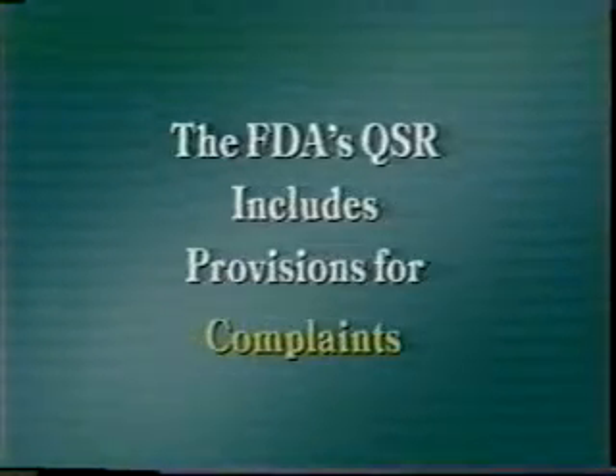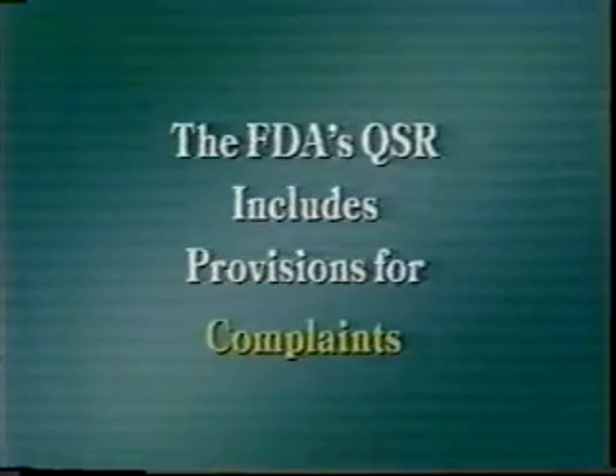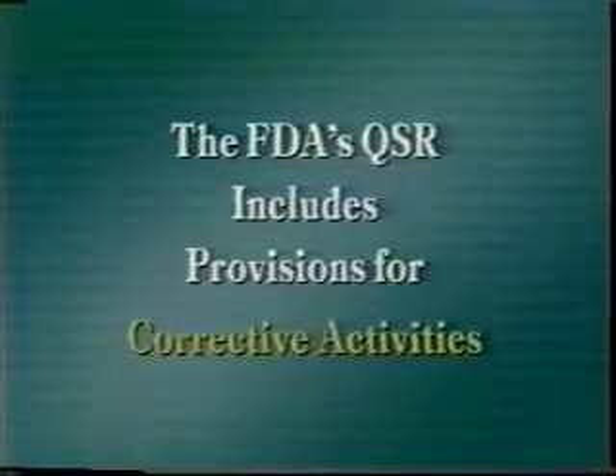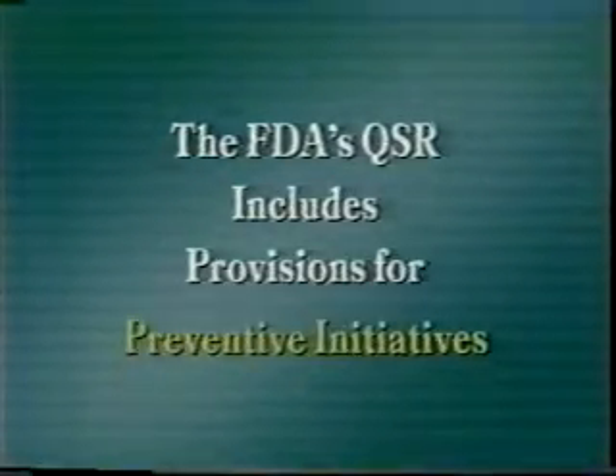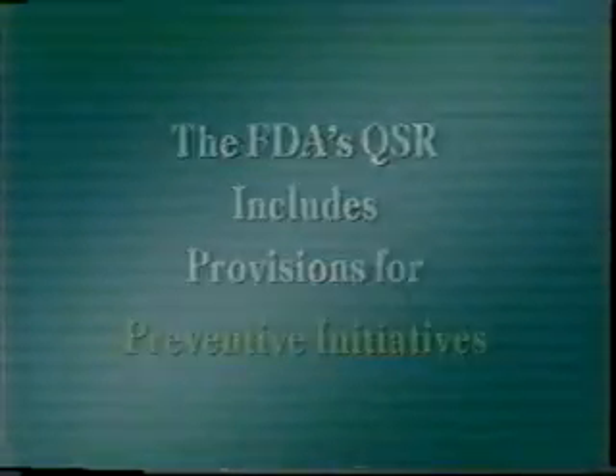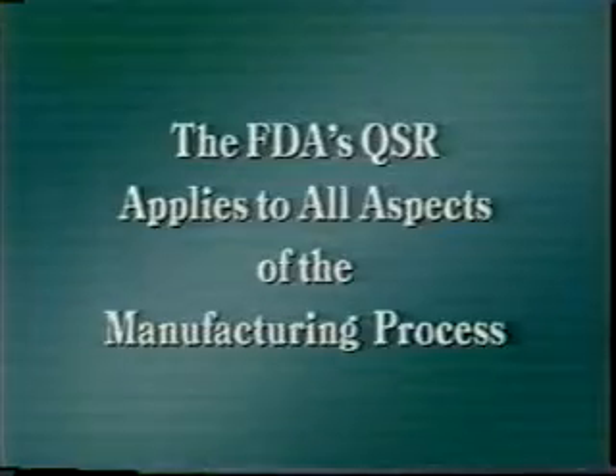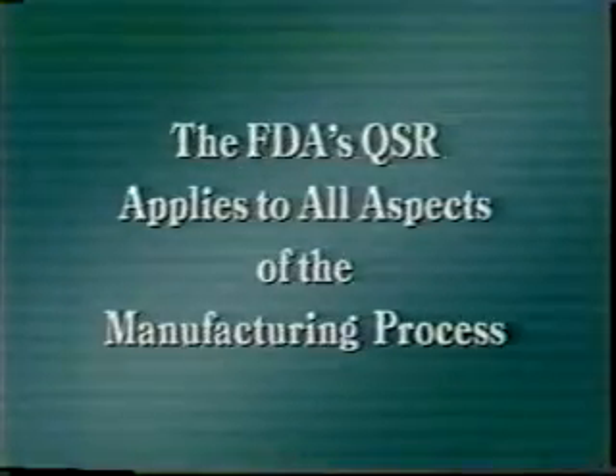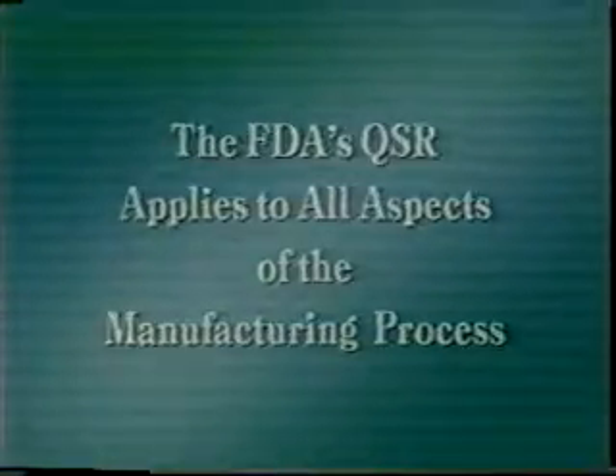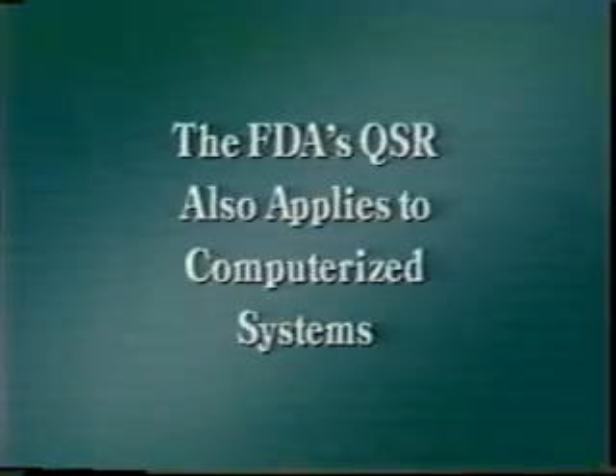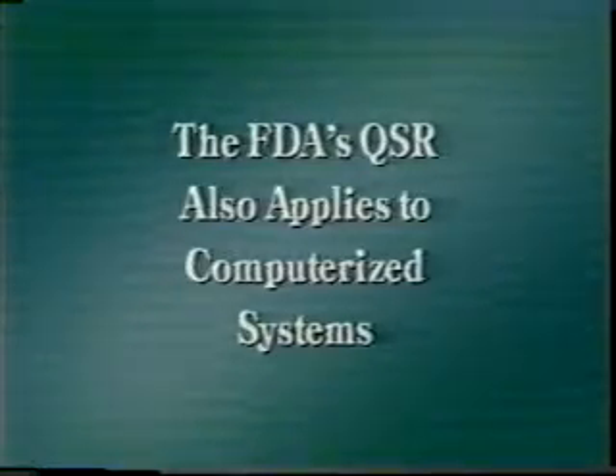The FDA, through its regulations, puts a heavy emphasis on problem areas during the manufacture of a device. And as a result, the QSR includes provisions concerning complaints, non-conformances, corrective activities, and preventive initiatives to make sure a product is not adulterated or misbranded. Finally, the QSR applies not only to what people do and the building in which they work, but also to all of the equipment. In addition, computerized systems that are used to run manufacturing and other equipment are subject to FDA's regulations. If a device does not comply with FDA's QSR regulations in a significant way, then the FDA will normally take one of 3 different kinds of enforcement or regulatory actions.